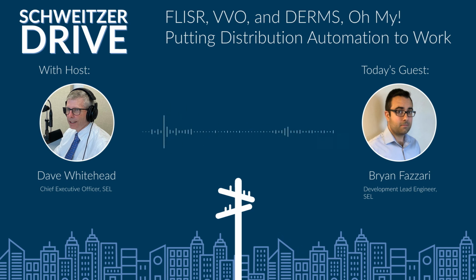So FLISR doesn't necessarily care how many meters down the line a fault is. It cares whether the fault is between switch 1 and 2, or switch 2 and 3, and so on—figuring out how to isolate it and route power around that outage area to minimize affected customers. The goal is to turn a potentially multi-hour outage for a lot of people into a much smaller outage, so the people we restore experience just seconds instead of hours.